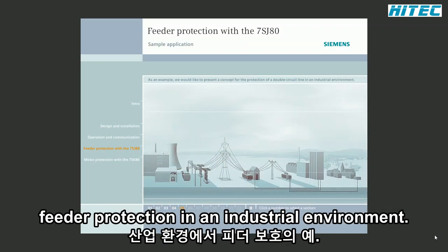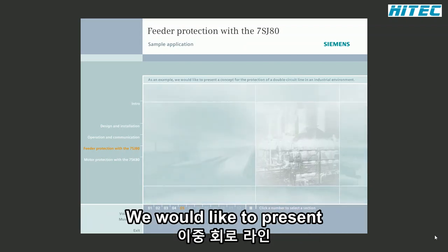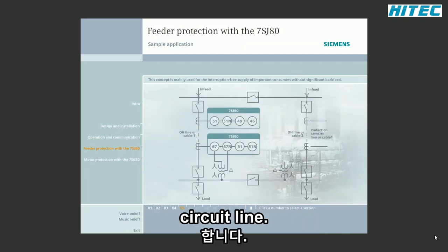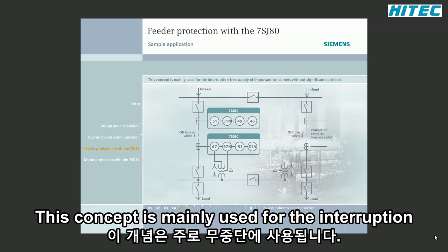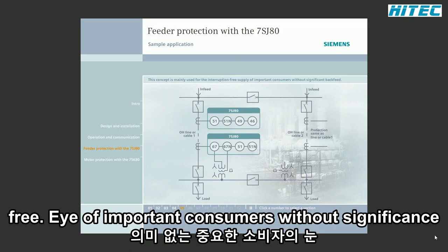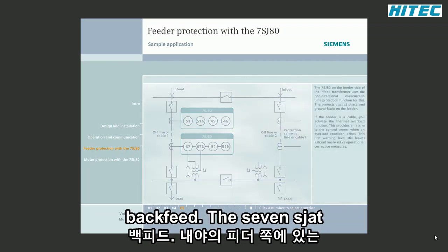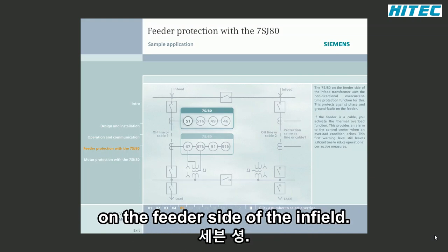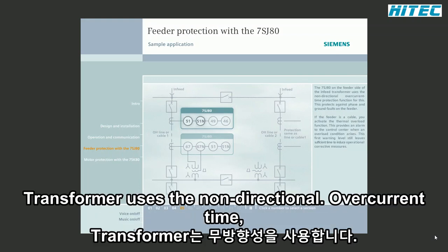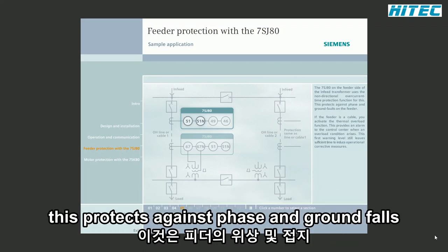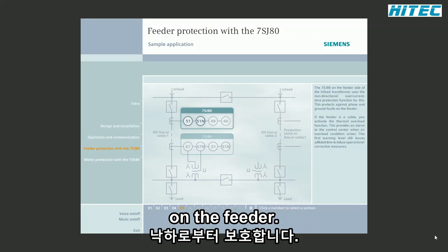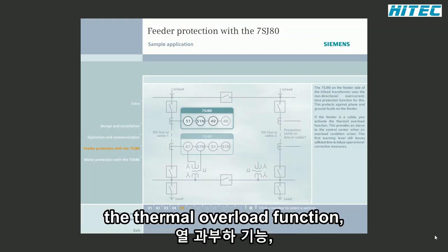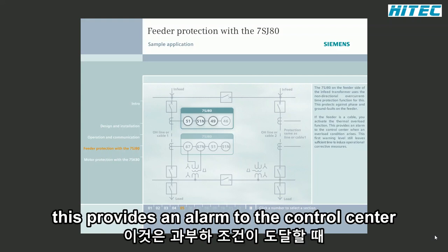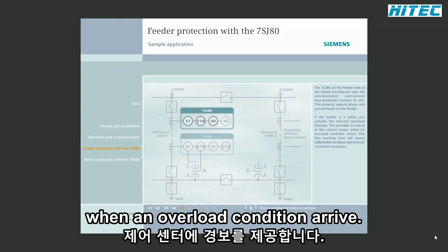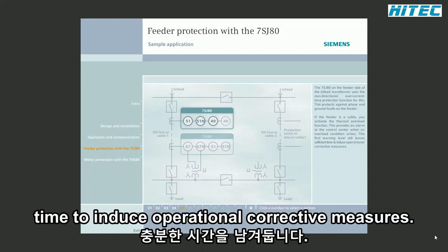As an example of a feeder protection in an industrial environment, we would like to present a concept for the protection of a double circuit line. This concept is mainly used for the interruption-free supply of important consumers without significant backfeed. The 7SJ80 on the feeder side of the in-feed transformer uses the non-directional overcurrent time protection function for this. This protects against phase and ground faults on the feeder. If the feeder is a cable, you activate the thermal overload function. This provides an alarm to the control center when an overload condition arises. This first warning level still leaves sufficient time to induce operational corrective measures.